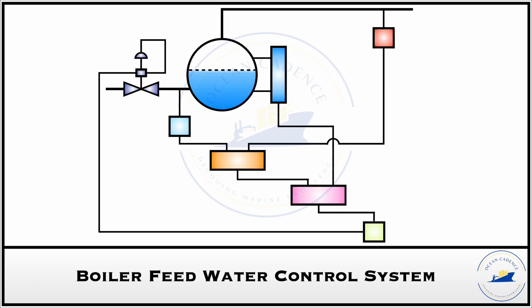So now to control this feed water mechanism one particular method will not be sufficient, that is one variable control will not be sufficient. Usually when I say that we have to control the level of the boiler our mind will straight away go to that okay we'll take a tapping from the level transmitter and when it reaches a certain point it will start and then again after filling it will stop. But no that is not sufficient because of the points that I told before. What we do is we add another elements into this particular feed control mechanism. So let us see how we do that.